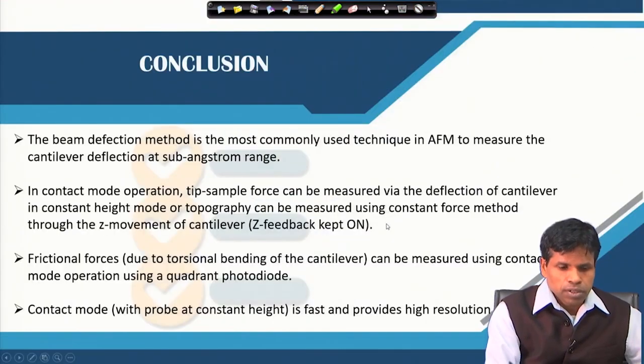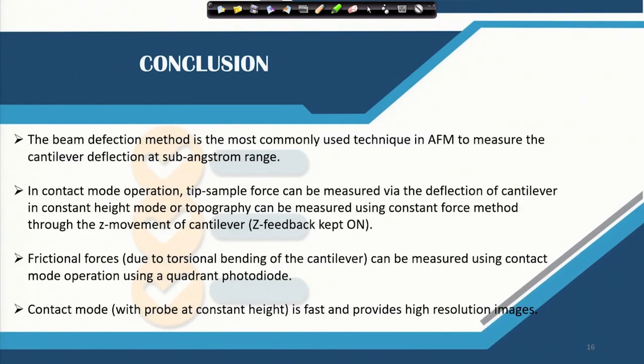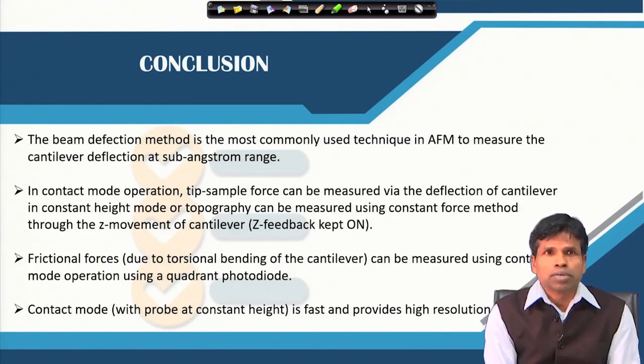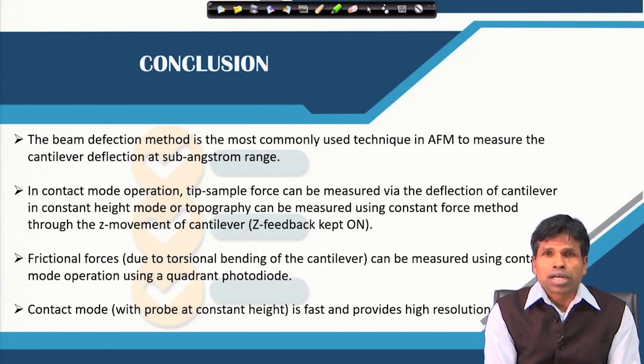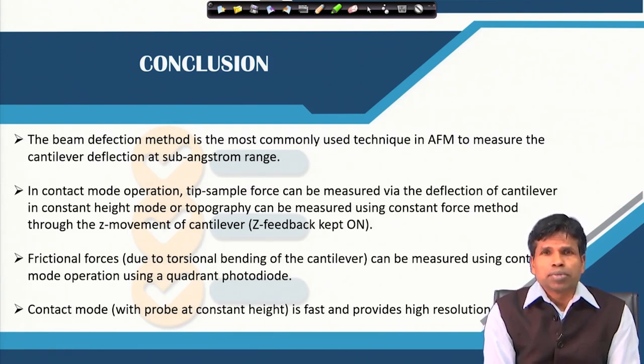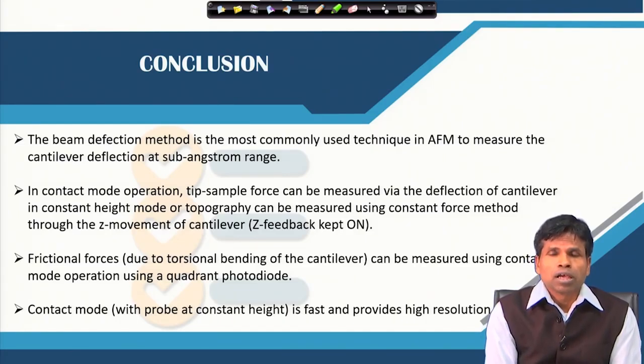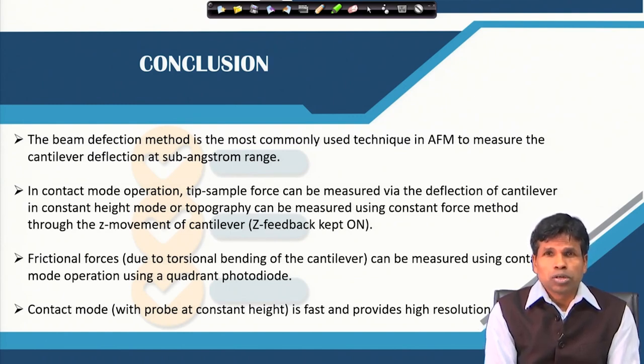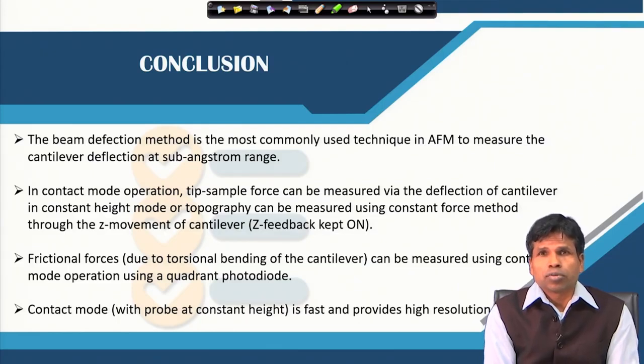In conclusion, the beam deflection detection method is the most common in AFM for measuring cantilever deflection. In the contact mode of operation, the tip-sample force can be measured via the deflection of the cantilever — either by constant height mode or constant force mode. Contact mode AFM allows study of frictional and lateral forces, is fast, and provides very high resolution images.